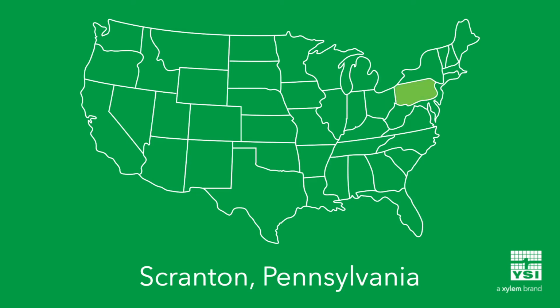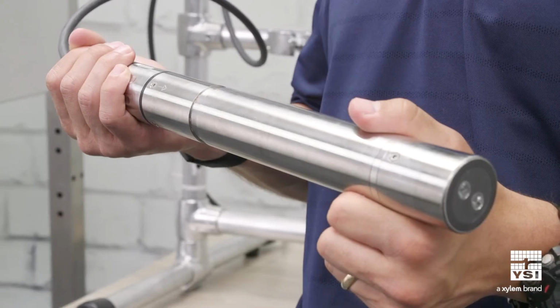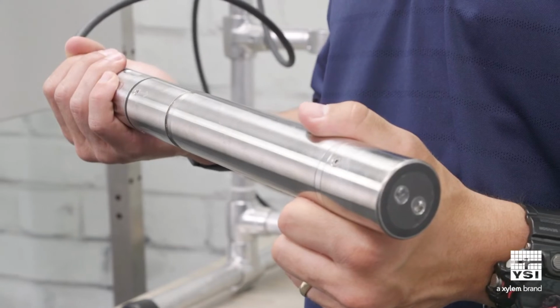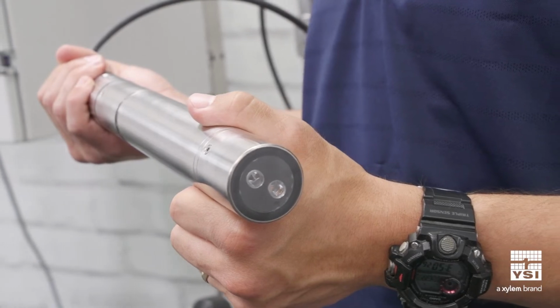Minimizing water loss in drinking water plants is an important aspect of day-to-day operations. Now, how is IQ SensorNet being used to keep excess water from being wasted? IQ SensorNet can help drinking water plants save water in many different ways. For example, a drinking water plant in Pennsylvania is using IQ SensorNet's turbidity sensor in their filter system to optimize their backwash cycle. Originally, this plant would run 2 20-minute rinses during their backwash cycle each day, and they would waste all of the water they used. Since installing the IQ SensorNet VisoTurb, they are now able to monitor turbidity measurement and stop the rinse cycle when they reach their target turbidity, which cuts down on the rinse time and saves a lot of water in the process. On average, this plant now saves 1 million gallons of water each day.